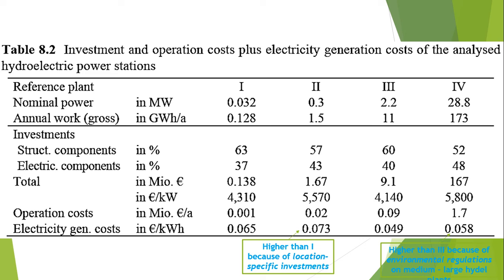Due to the high investments, lower generation cost can only be achieved at full load hours that exceed those assumed within this example, and at very low cost for the plant operation, for example in the case of private ownership. In contrast, the analyzed small hydroelectric power station with a capacity of 300 kilowatt — that was plant 2 — costs around 0.073 euros per kilowatt hour.